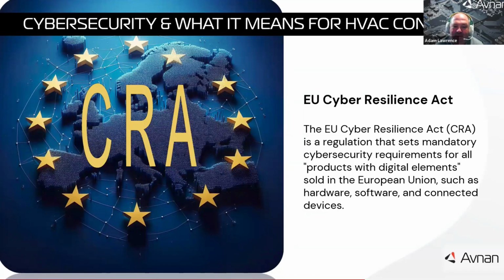And finally, one thing that's possibly flying under the radar for many OEMs, the European Union Cyber Resilience Act. This regulation, which will come fully into play by late 2027, will require every connected controller sold in Europe to be secure by design, supporting encrypted communication, authenticated firmware updates, and in some cases, third-party certification. Even if you don't sell in Europe today, this is going to shape expectations globally. The writing's on the wall. If your controller connects to the internet or building network, it's going to need stronger cybersecurity controls, secure firmware, and traceability mechanisms.